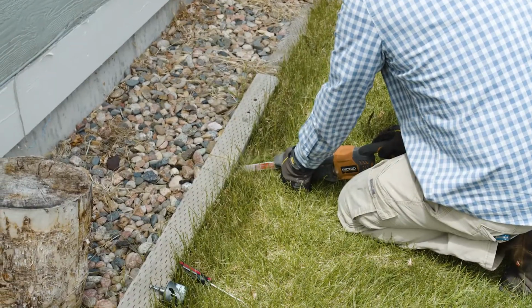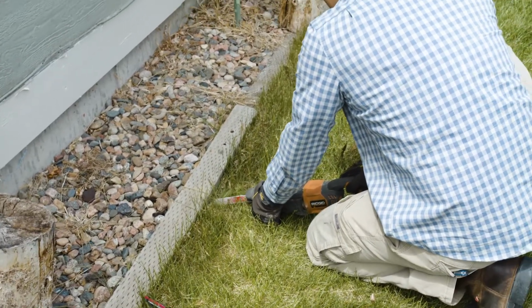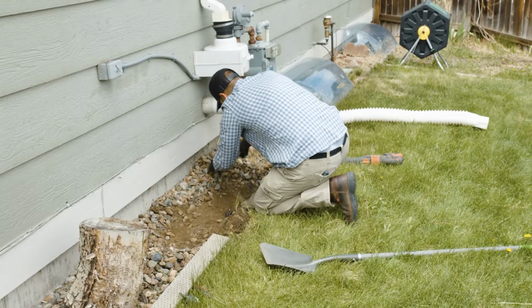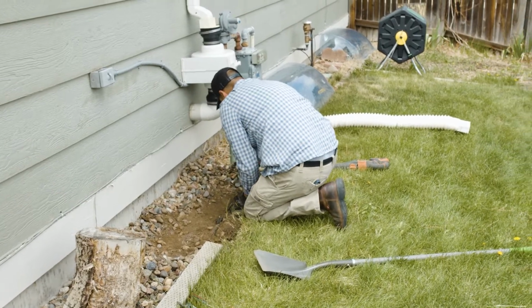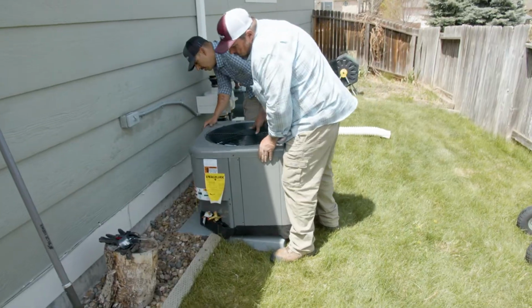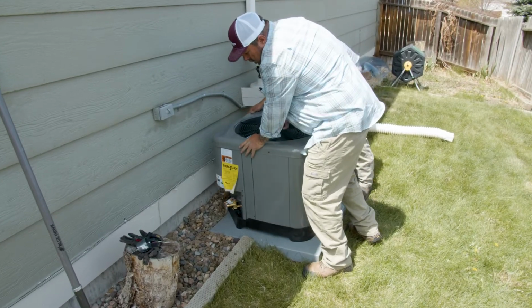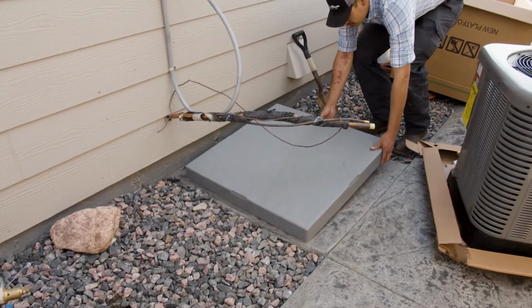The next step in the process is to get the outside pad leveled for the condenser. Normally we'll have to move all of the rock or gravel out of the way, get down to dirt, level everything out, set the pad, and then put the gravel back and make everything look nice and neat for you. On this home, we don't really need to do much, just set the pad down and get it 3 inches above grade.